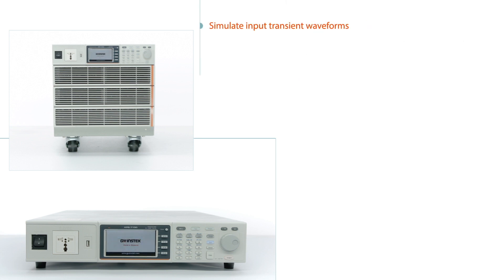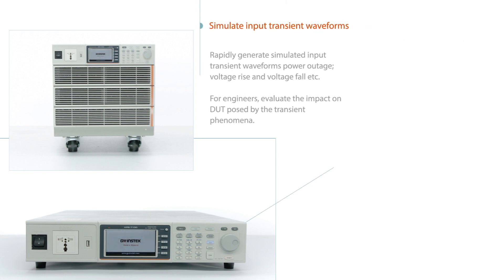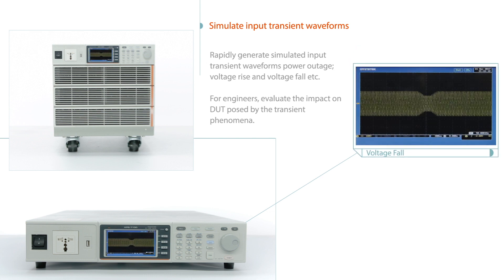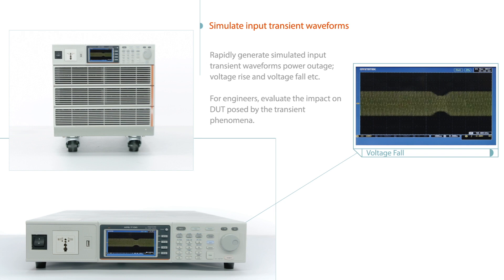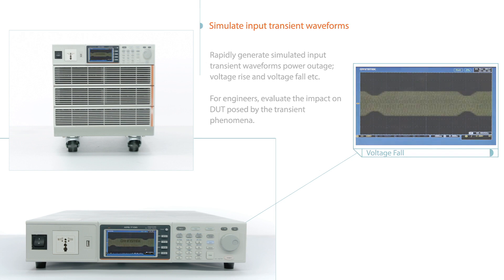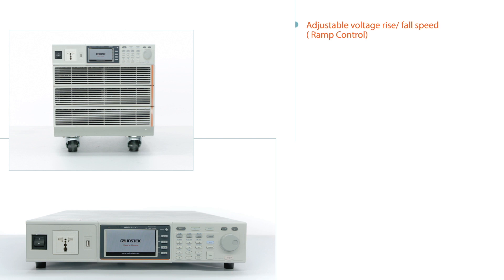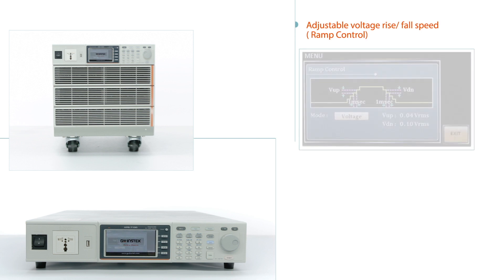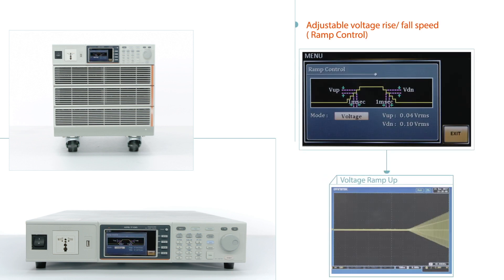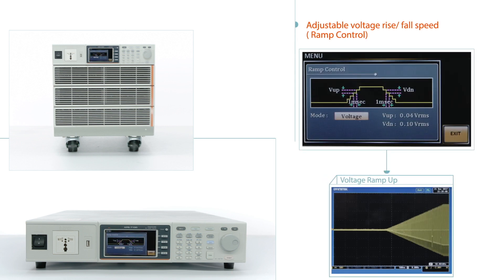This mode can rapidly produce different simulated input transient waveforms such as power outage, voltage rise, and voltage fall, for engineers to evaluate the impact on DUT posed by transient phenomena. Ramp control allows users to set output voltage rise or fall speed, which is based on time or voltage.